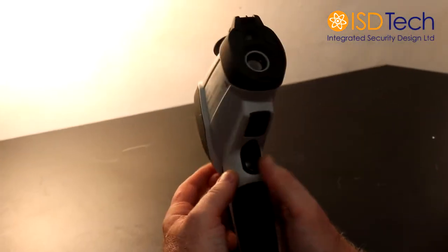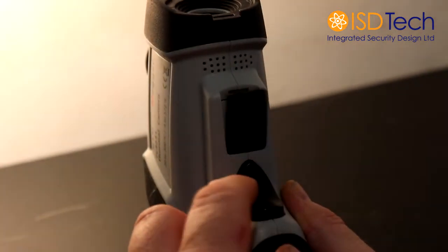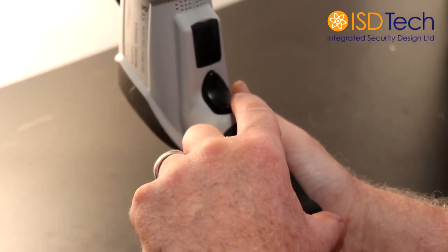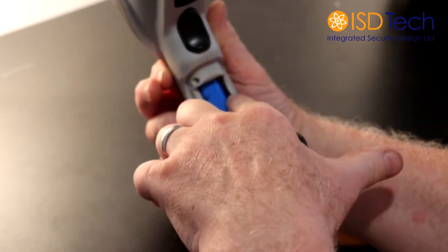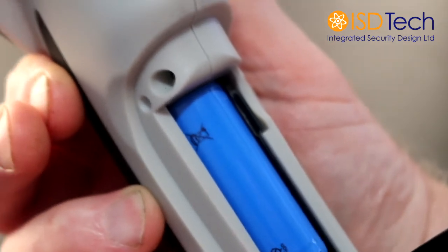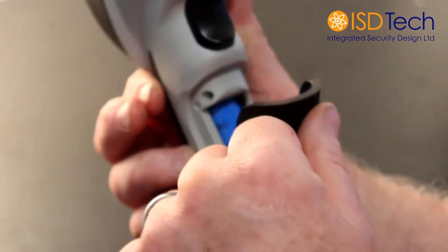The TC3231, seen from the front and from the underneath. This little flap here has your USB charging point. This is the trigger for taking the temperature reading and recording it on the SD card. And within the grip is the SD card, top right-hand corner as you look at it, and the battery. The battery is rechargeable — it's a lithium-ion battery. It should not need replacing for quite a few years.